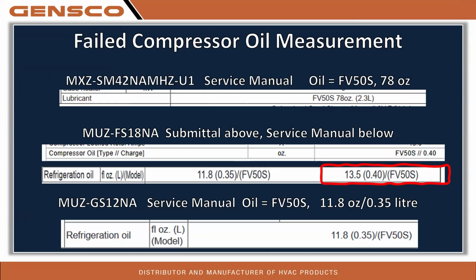Now, if it is a scroll compressor, you're still going to have to drill a hole in it. The older scrolls, you could tip them over and drain it out of the suction line. The newer scrolls, you cannot. It won't come out. So you have to drill a hole in the bottom, drain the oil in something you can catch it with that can also measure it. And we're looking for something close to this number.